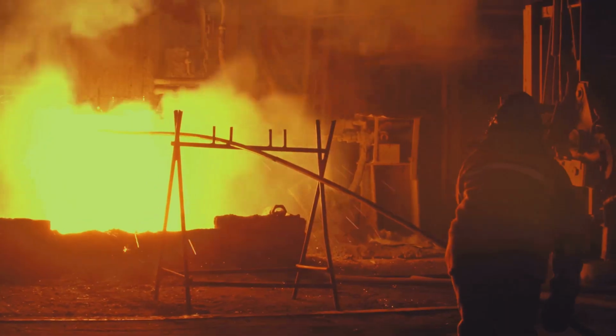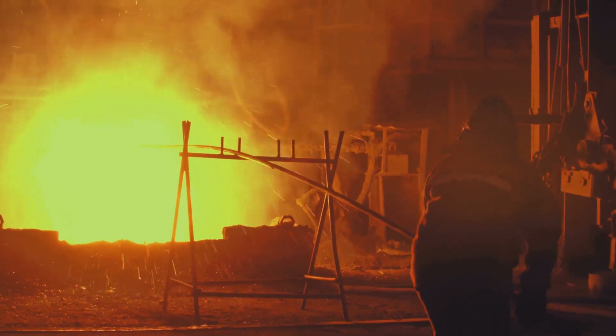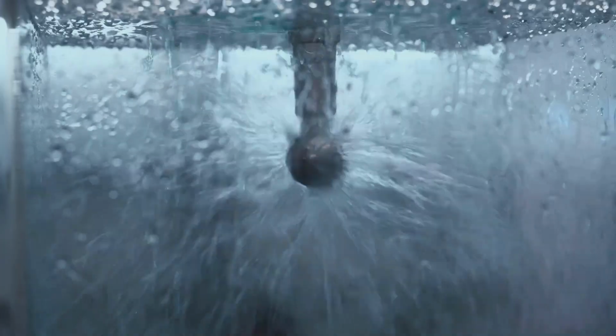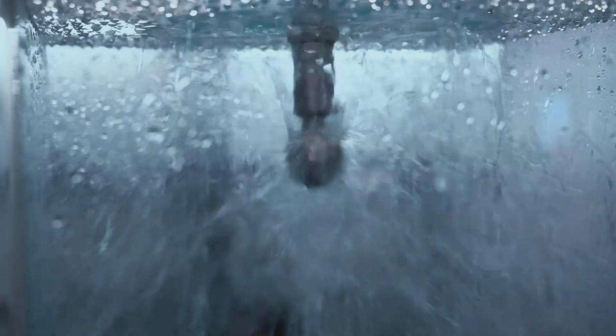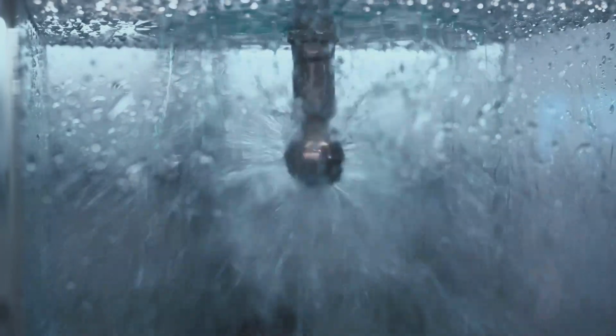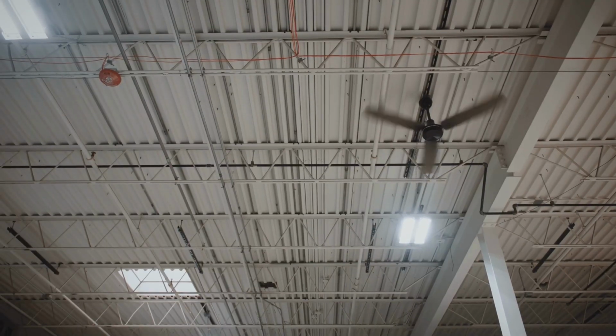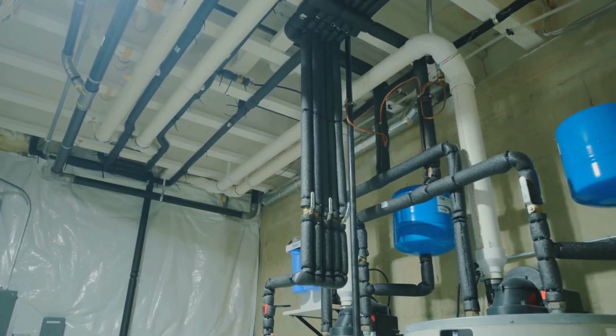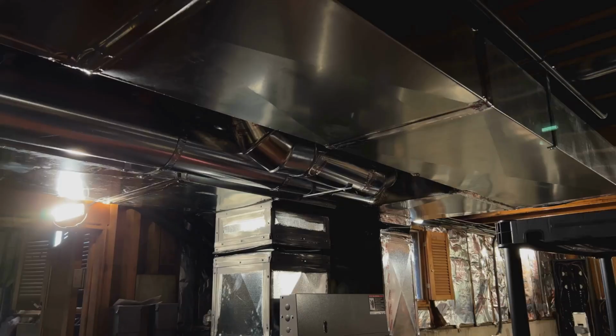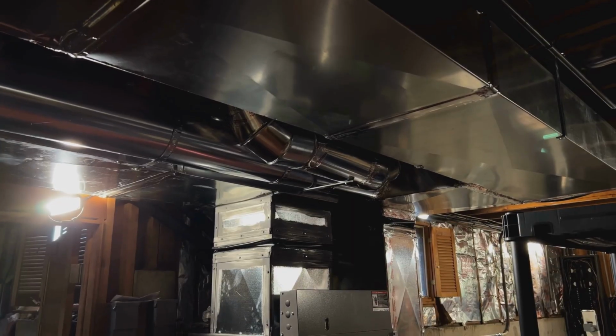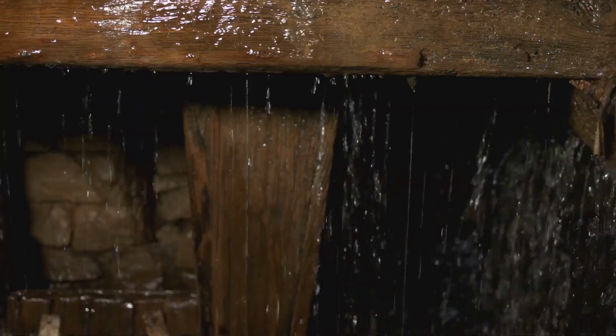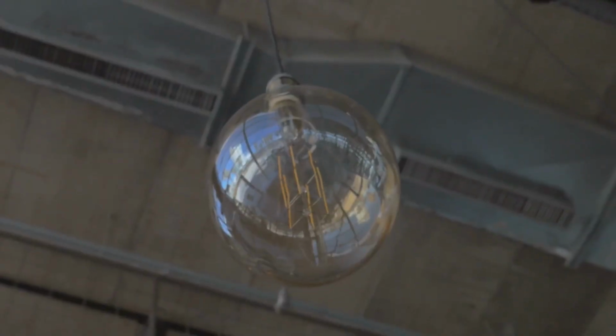If you've ever seen a fire in a movie, you've probably seen this happen. A single sprinkler goes off, and suddenly every sprinkler in the building starts spraying water everywhere. It looks dramatic. It also isn't how real fire sprinkler systems work. In reality, most fires are controlled by just one or two sprinklers, not the entire building. So how does that actually work?